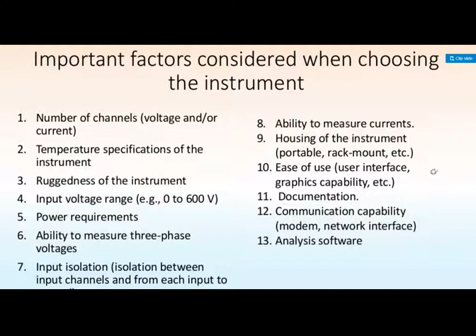Sixth is the ability to measure three-phase voltages. Seventh, input isolation between input channels and output channels. Eighth is the ability to measure currents. Ninth is the housing of the instrument, whether it is portable or rack mount. Tenth is ease of use, the user interface and graphic capability. Eleventh is the documentation of the equipment. Twelfth is the communication capability, using modem, network interface, etc. And the last one, which is the most important, is the analysis software for analyzing the data gathered by the measuring instrument. So these are the main factors considered while choosing a power quality measurement instrument.